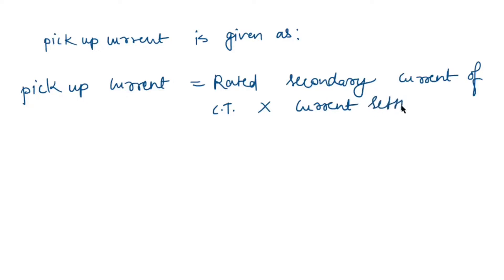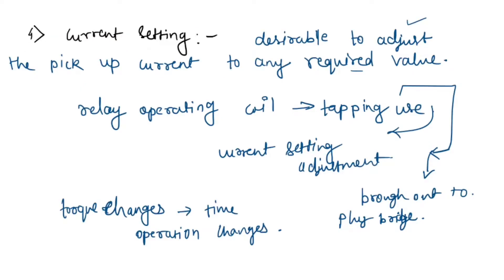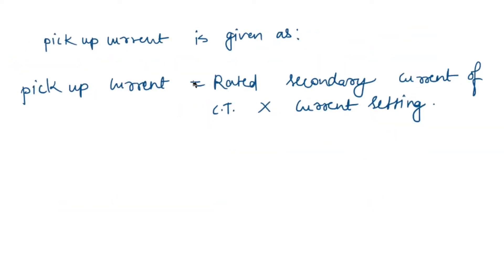The pickup current formula is: pickup current equals the rated secondary current of the CT multiplied by the current setting value. So pickup current is determined by the current transformer secondary side rated current and the current setting.